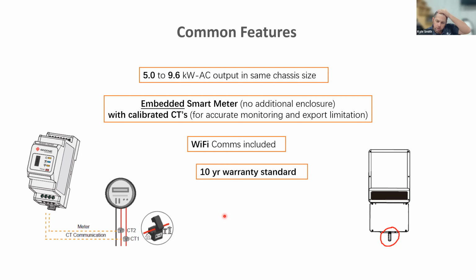Does LAN require anything special? Just anything on that front? Yeah, good question. Instead of plugging in the dongle device you see here, you'd be plugging in a different one, but after sales would send that to you, knowing that that's what you need. We know at the residential level it's not very common, so we don't throw one of those in the box. But if you need that, in your quick start conversation, when you first talk to support after sales, they will ask about this. And if you say, well, for this install we're actually going to use a LAN connection, great, we'll send you one in advance of you going out there.